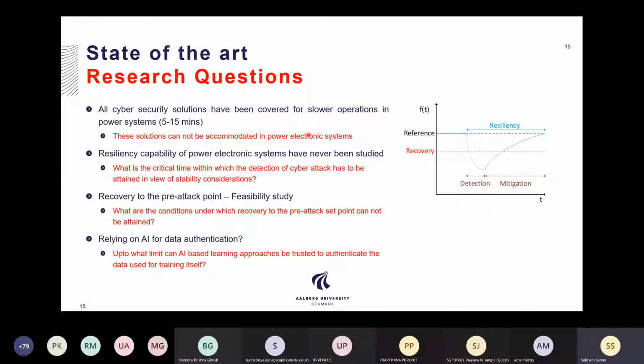All the cybersecurity solutions covered so far have been for slower operations in power systems, that could be from 5 to 15 minutes. But these solutions cannot be accommodated in power electronic systems, even at 1 minute, because any false data, denial of service, or denial of signals for even milliseconds could be a big problem, since the control system expects signals in real time, within maybe a few milliseconds or microseconds. So that could be harmful.